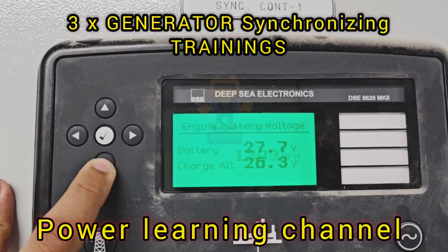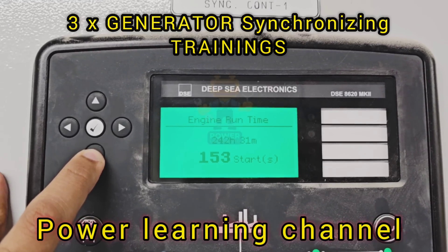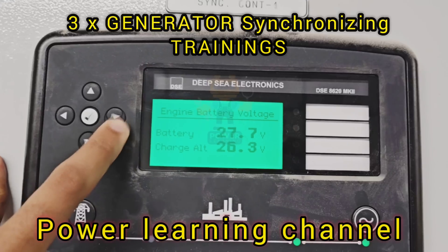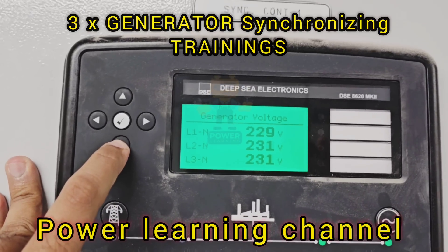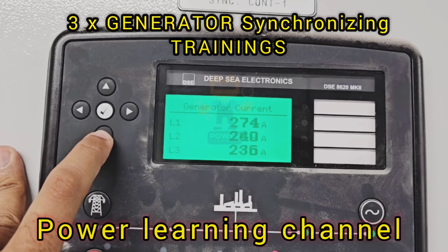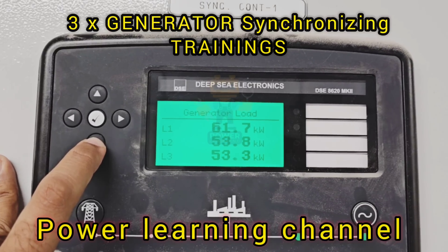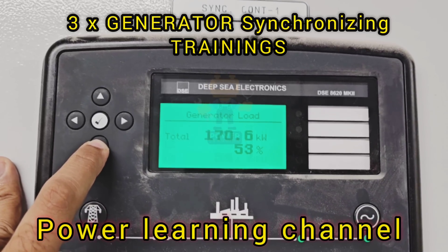Let's go a bit deeper into how the synchronizing process works with the DSE 8620 MKII controller. The process begins with the generators running independently. Each generator starts up and reaches its operating parameters under the control of its DSE 8620 MKII module. Once the generators are running, the controllers start to communicate with each other, exchanging data about their respective generator voltage, frequency, and phase angle. The controllers then begin the process of aligning these parameters, adjusting engine speed to match frequencies and making fine adjustments to voltage output.